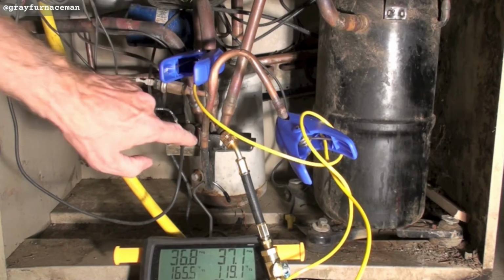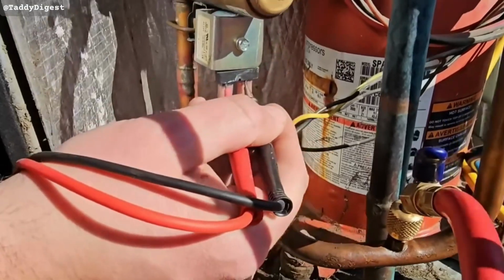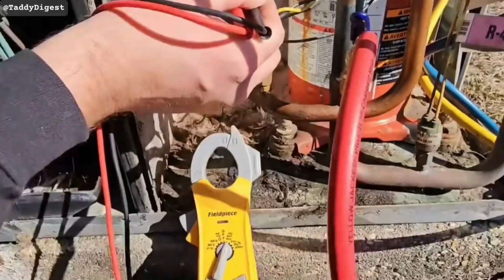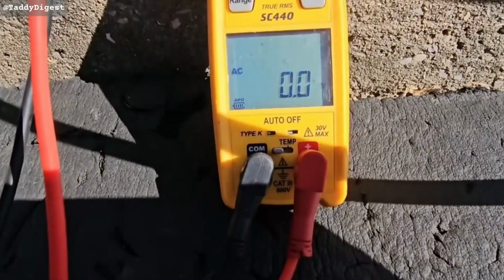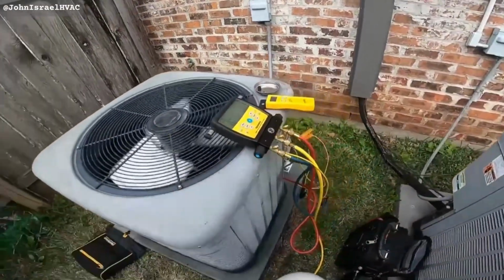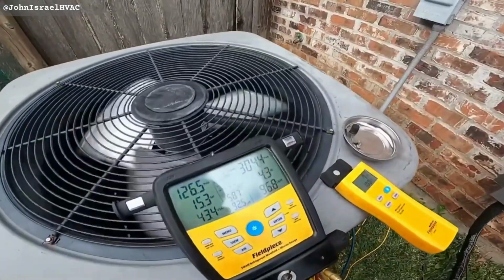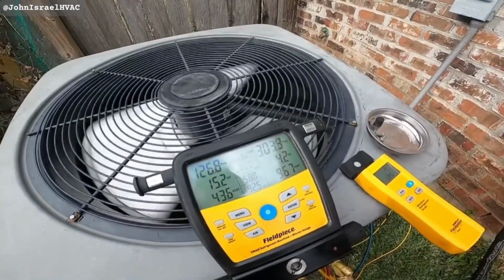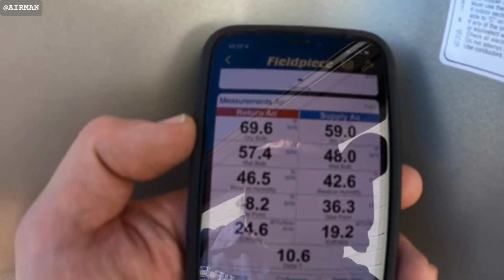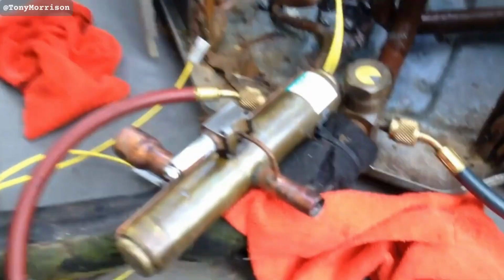Symptom is reduced capacity in either heating or cooling mode, but not both. The diagnostic is a temperature split test in both modes. Cooling mode should show about a 16 to 22 degree drop across the indoor coil. Heating mode should show about a 20 to 30 degree rise. If one is off and the other is normal, the reversing valve is your suspect.